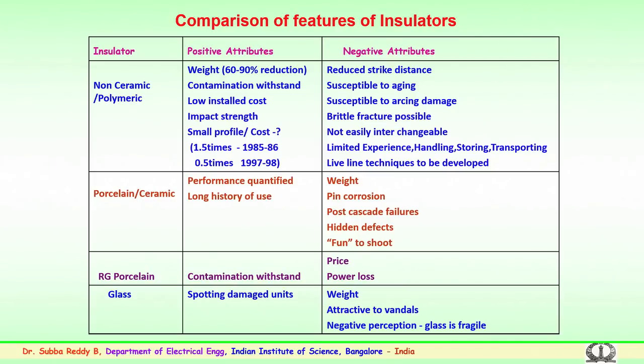The porcelain or ceramic performance has been quantified, with a long history of use of more than 100 years. The negative is the weight; compared to polymer technology, the weight is higher. Then pin corrosion failures are observed. There are failures because of post cascade failures and some hidden defects in ceramic insulators, particularly at the pin junction, because of crack formation or cement growth. These are failures which cannot be observed by the naked eye. And in places where there is vandalism, where both ceramic and glass insulators are installed, there are vandalism failures, and a lot of maintenance cost has to be considered at those places.